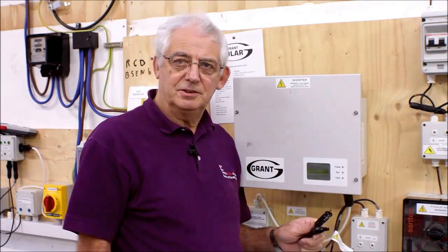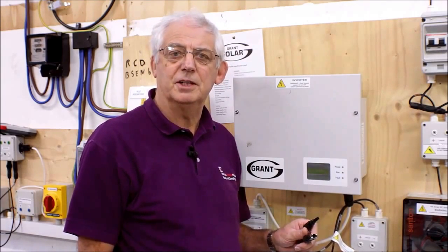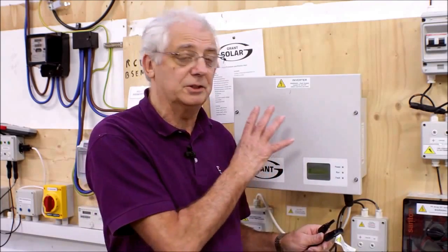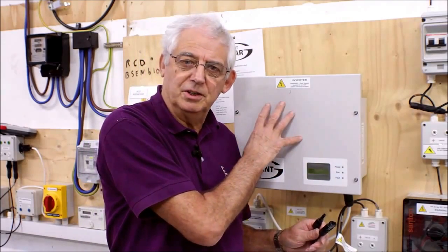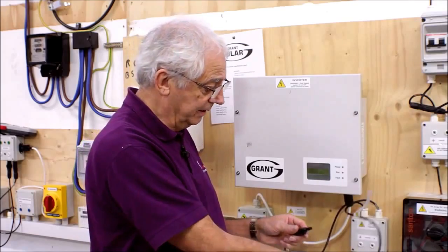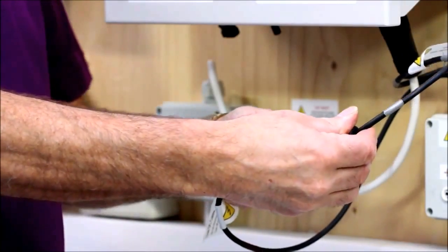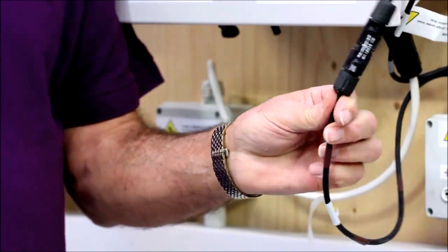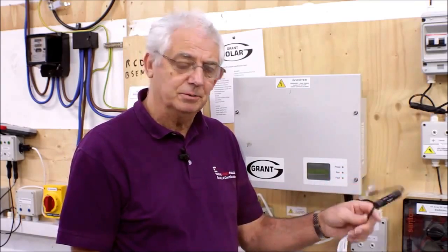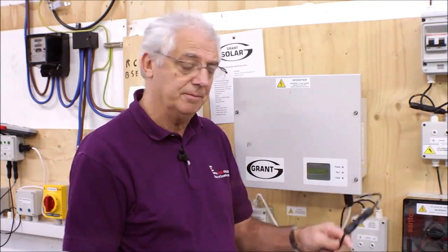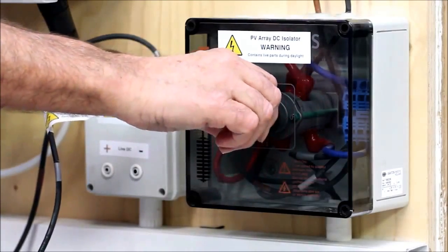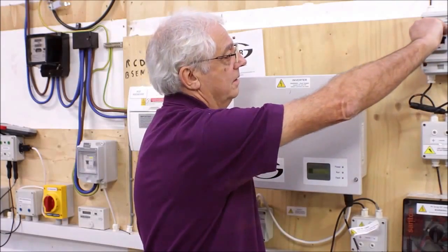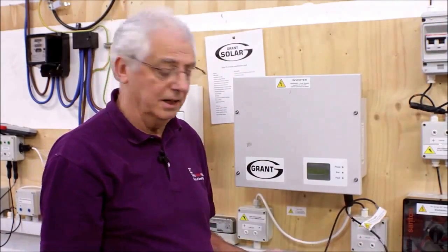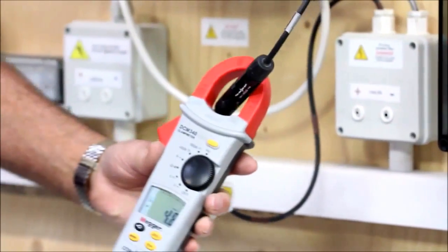Having calculated the value of current I'm expecting, I now need to short circuit the system and take a measurement. So first of all, I need to make sure the inverter is isolated. I then join the plug and the socket from the panels together, therefore creating a short circuit. I turn on the isolator, and then with a clamp meter, I need to take a measurement.